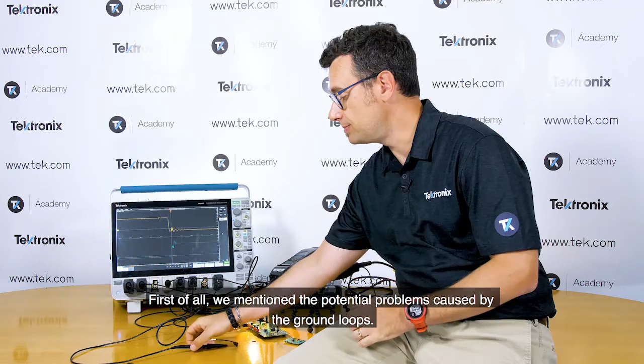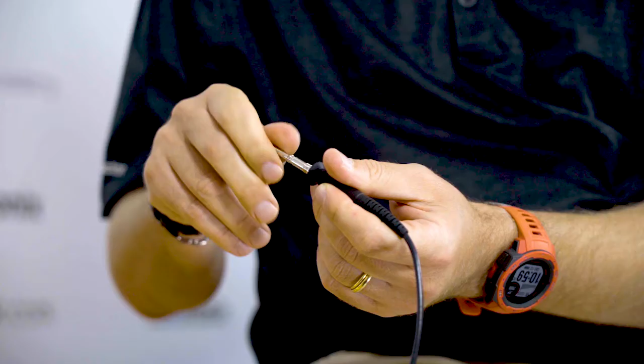First of all, we mentioned the potential problems caused by ground loops. Here is a typical probe configuration with this long tail, and we discussed there is an inductive effect from the ground tail here. So what can we do about it? As we have seen, we can simply modify this probe by replacing the tip with one that implements the coaxial MMCX connector we discussed about.